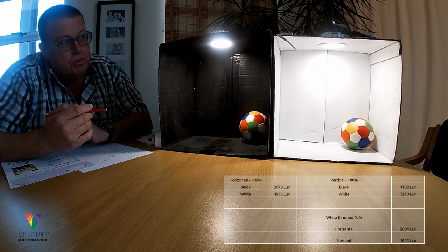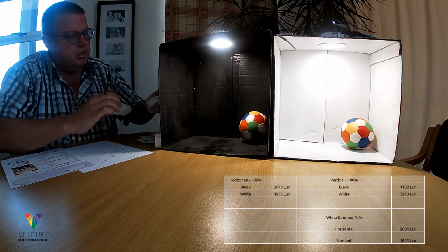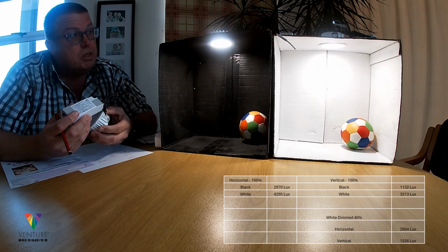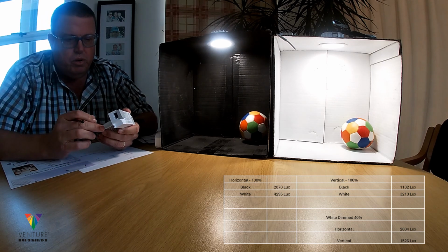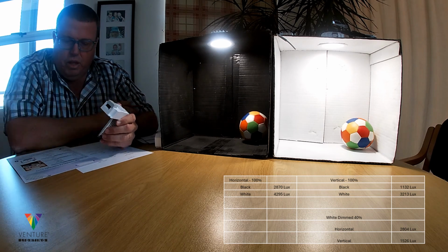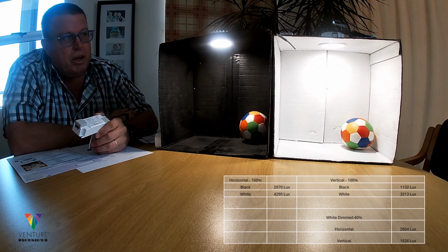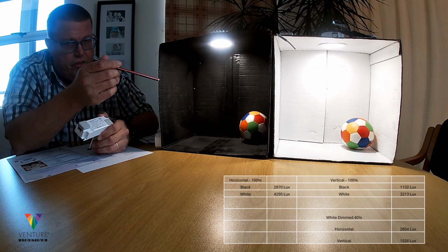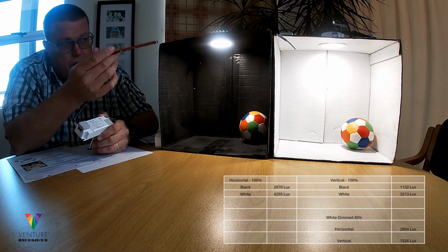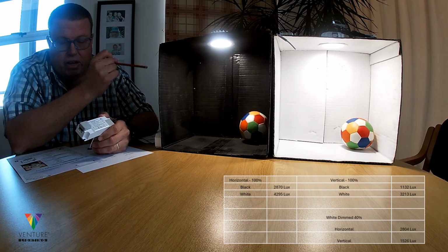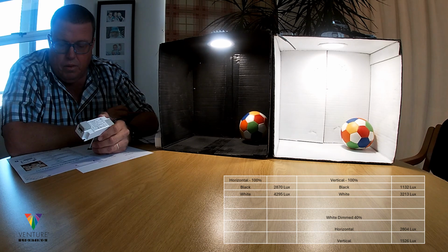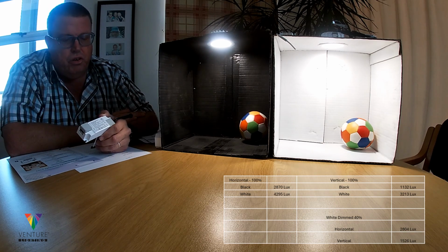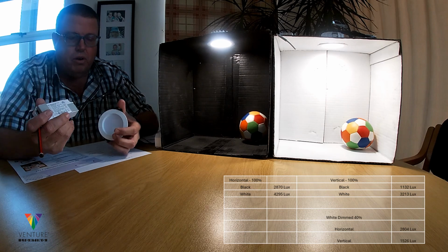Before I give you the results, I just want to show you what product I'm using. I'm using our latest range of downlighters called the Luminaflex. This one installed here is a 5-watt Luminaflex downlighter, 110 lumens per watt, color rendering about 83. In fact, I've measured all of these with the spectrometer, and the luminaire's color rendering index is 86. So 110 lumens per watt, 100 degree light distribution, 19 UGR, and it's a dimmable driver as well.